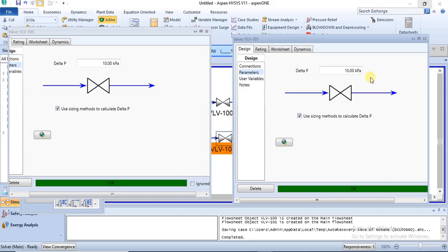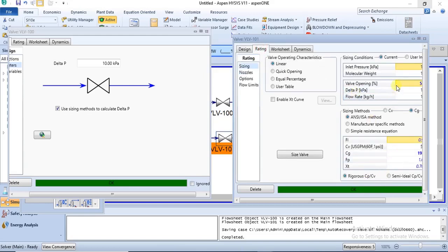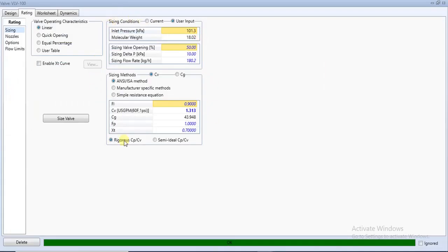To summarize the workflow: first, simulate your valve until it solves; then size the valve; then go back to the Design and Parameters section to remove the initially specified pressure drop, and allow HYSYS to calculate the required pressure drop based on your sizing details. If you later change any sizing details in the Rating section, you will need to size the valve again and a new pressure drop will be calculated.